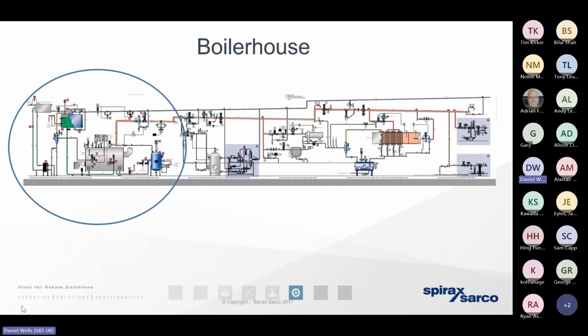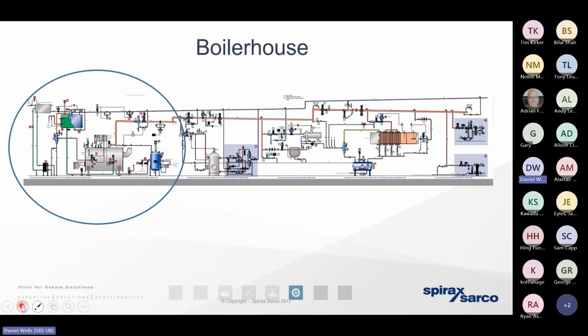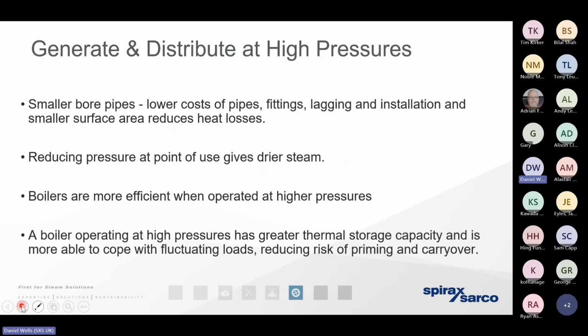Okay, so I'm going to start off by visiting the boiler house, steam generation. So as we've mentioned in previous presentations, our client is likely to have anywhere between 2 and 6 of those horizontal fire tube steam boilers. Typically, they're going to be operating at a pressure somewhere between 7 and 12 bar gauge. And we can then be distributing that steam thousands of meters around site to supply the heat energy for the various processes. So the best means of generating the driest steam that we can really means that we need to look at how we're operating the controls of the boiler itself.